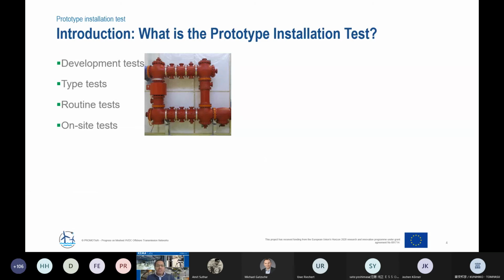Coming to the prototype installation test, there are different types of tests, and the prototype installation test is a kind of unique and special test. Other tests, for example, could be a development test, where the focus is the use of equipment for a new or special service, or new development, which is normally performed at the manufacturer. And there's the type test, performed at an independent laboratory, which focuses on verifying the rating of specified equipment.